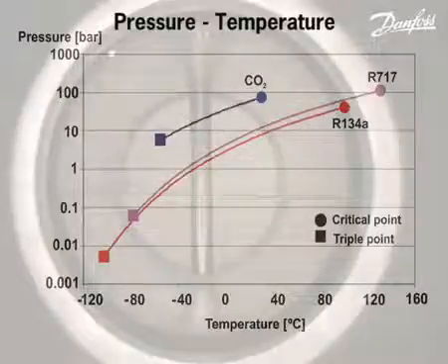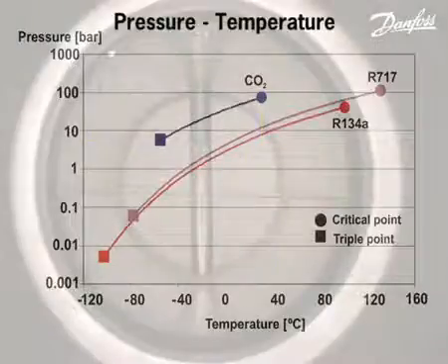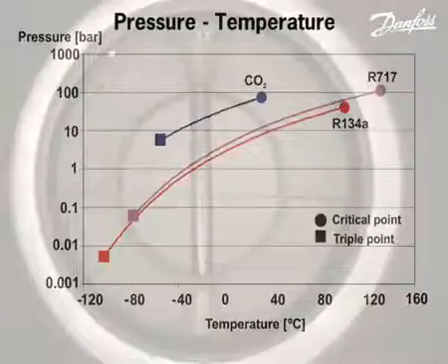The pressure at the triple point is high and the temperature at the critical point is low. These facts must be taken into account when CO2 is utilized as a refrigerant.